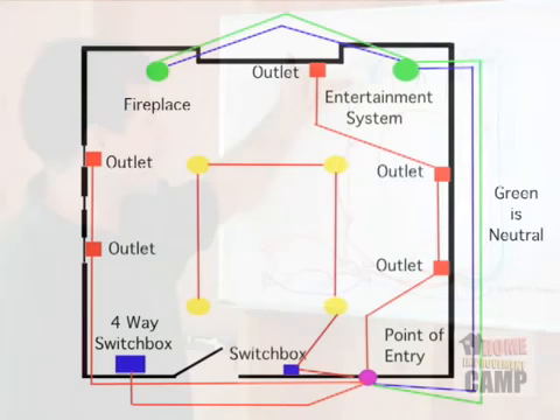The fireplace is a dedicated appliance circuit. It's not going to require the arc fault circuit interrupter, but you may want to check the codes in your area and talk to the inspector, because he could require it. So we've got our three circuits: our red circuit, our blue circuit, and our green circuit. Those are going to be home runs back to the circuit breaker panel.